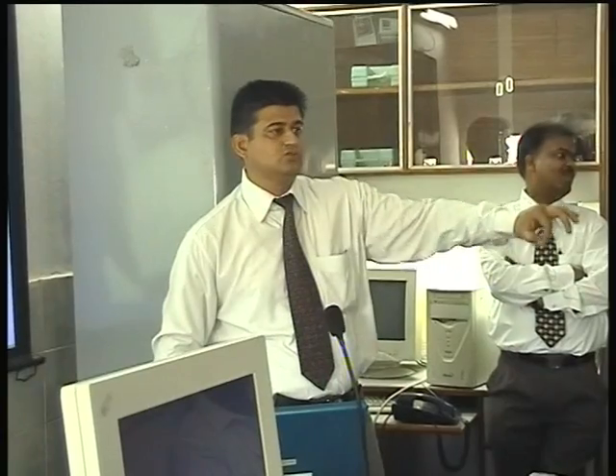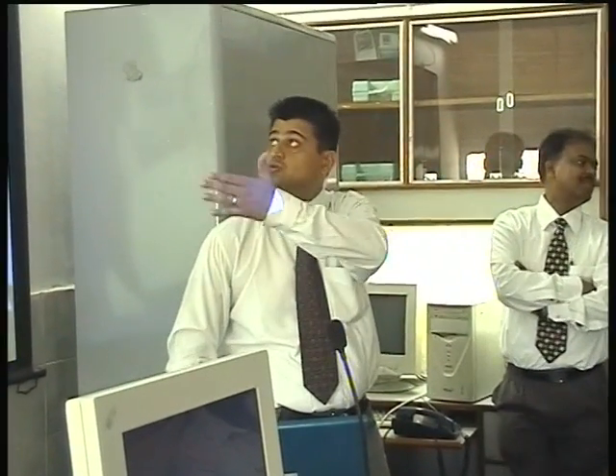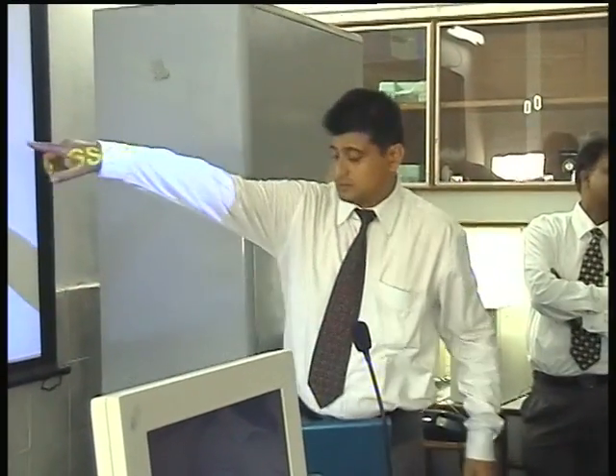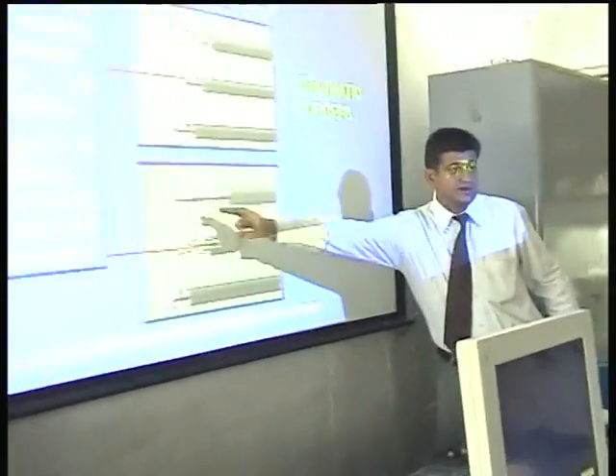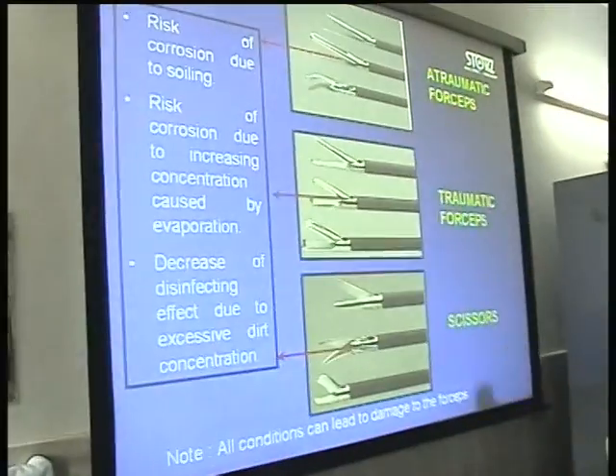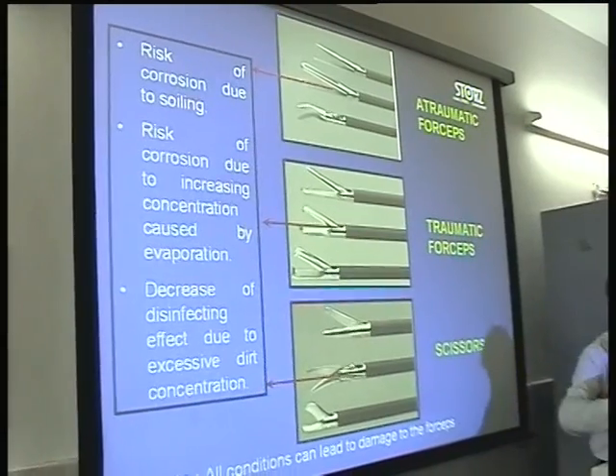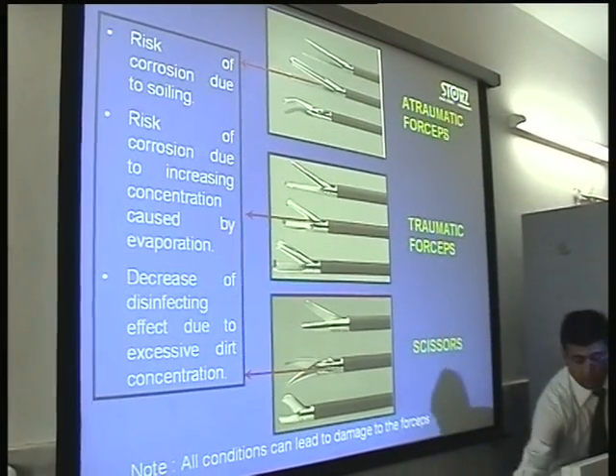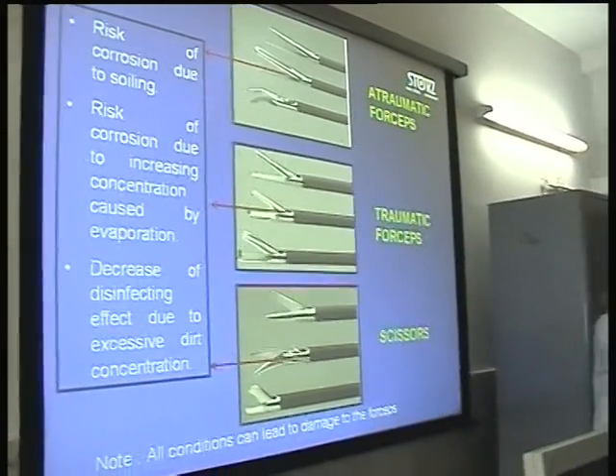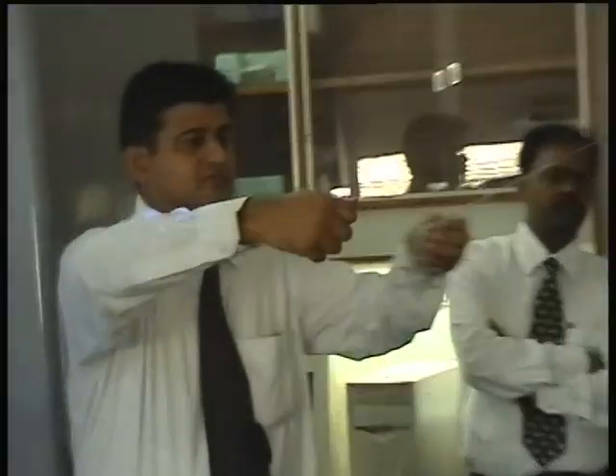Once you put the cleaning agent into this and it starts vibrating, it will clean the blood and the debris in the nooks and corners of the instruments. So you can use these gadgets. Similarly, the blood debris getting over here can be cleaned over there. The instrument has to be dismantled. I have seen that once the instrument comes from the OT after the surgery, nobody opens these knobs. These knobs have to be opened, these screws have to be opened, you have to dismantle and then clean it. Then only you have better access.